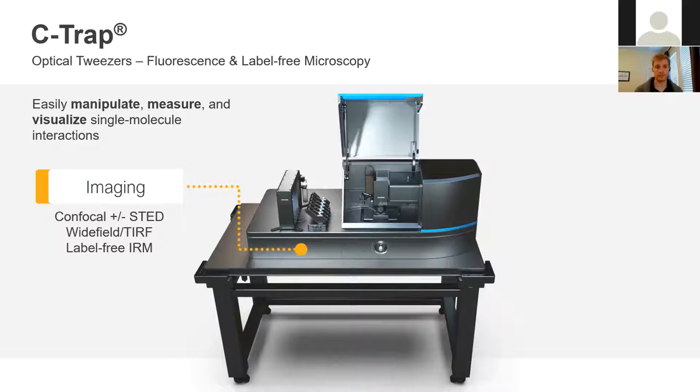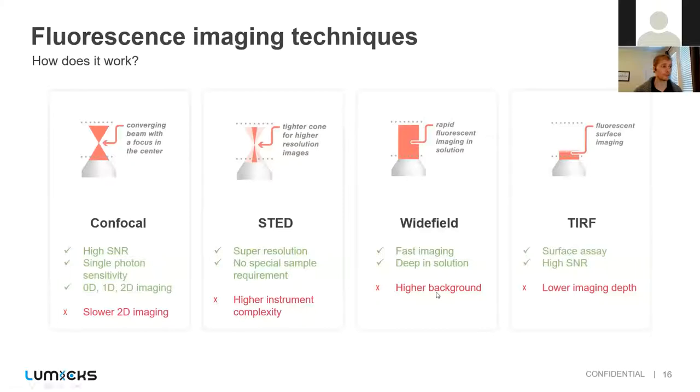So with this, you can have different setups. One is the confocal. So confocal is great, because you can have high signal to noise ratio. We've designed ours to have single photon sensitivity, so you can detect individual molecules. And then you can also do things like point scans in 0D, line scans in 1D, or 2D images. The downside here is with confocal, you're scanning a piezo over the sample so it can take longer.